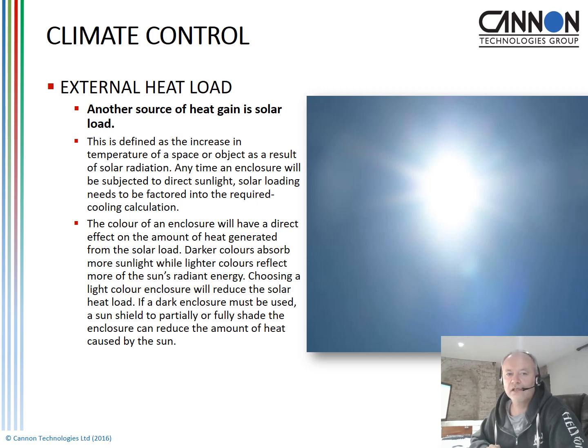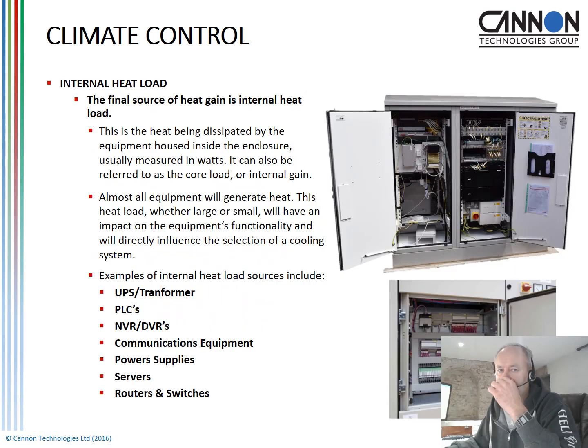So choosing a light colour for an outdoor cabinet is advantageous because it will help reduce the amount of heat load, and we do take the colour of your enclosure into the calculation. Obviously, a lighter enclosure can negate the need for a sun shield. We also look at whether it's in shade, because if the sun is not directly on it, there's going to be a reduction in solar heat gain.